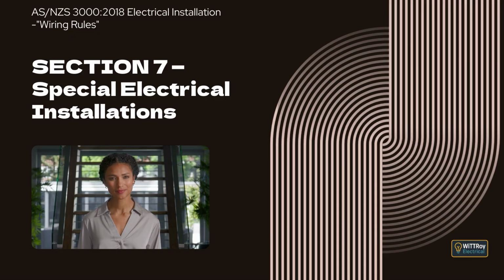7.5.9.1, General. This clause explains that every extra low voltage circuit must be individually protected at its origin against overload and short-circuit currents using a suitable protective device. The protection must comply with the general requirements for protection against overcurrent. It also explains that where the extra low voltage supply is earthed at the point of supply, protective devices must be installed in all unearthed conductors. Certain circuits arranged under specific conditions may not require overcurrent protection.